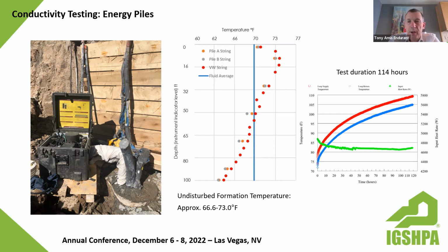With an energy pile, the conductivity test isn't a 24 or 48-hour process, it needs to run for a lot longer than that. You've got to see the curve really start to dip, so on a very large diameter pile you could be waiting for quite some time.